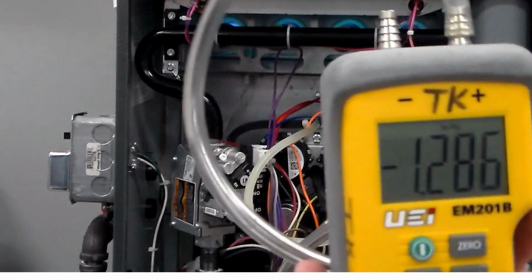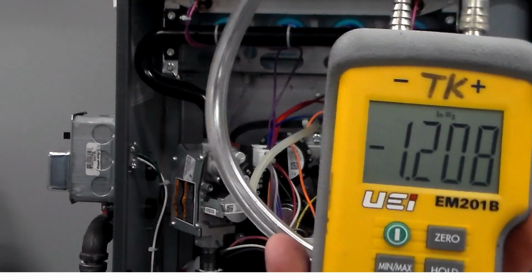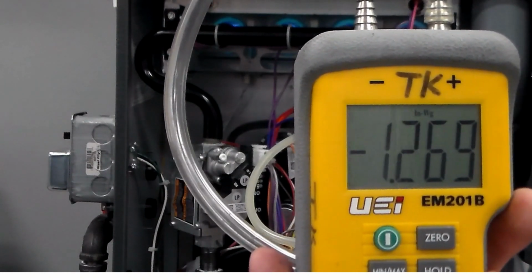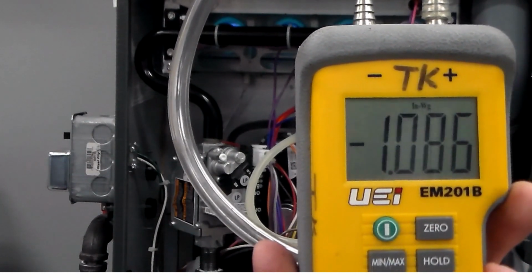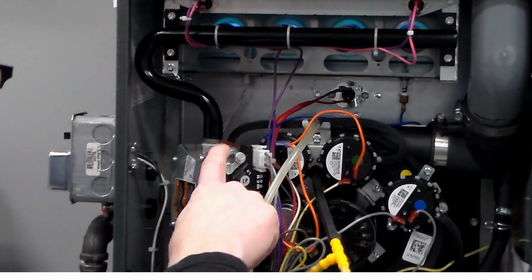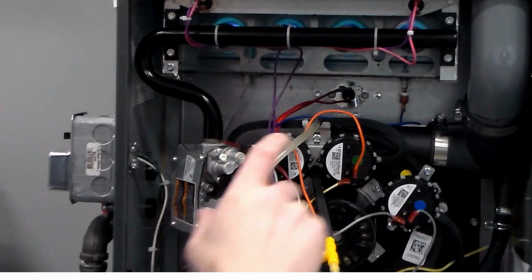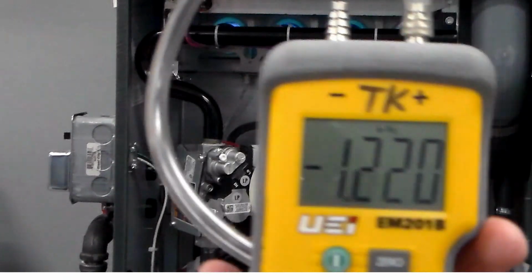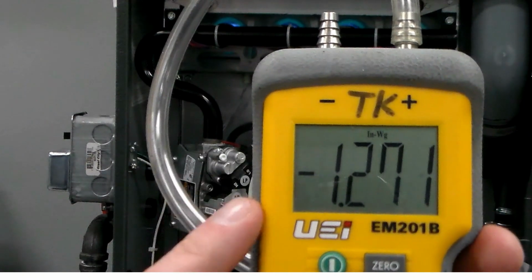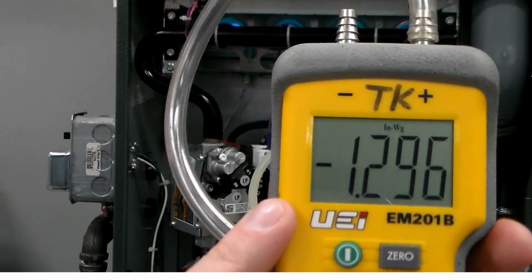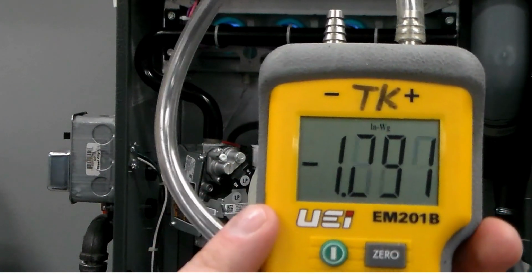Another reason that I mention this too is sometimes, especially on units that use full current through the pressure switch, you will sometimes see or hear the gas valve chatter. You'll see the chatter in the gas valve, you'll see the flames flickering sometimes, and if you have a manometer connected to that draft reducer, you will see that your draft is getting very close to the setting of that switch.